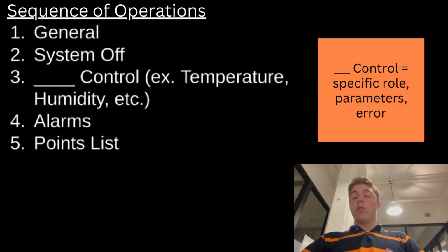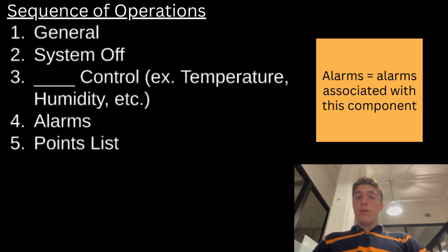3, blank control. So this could be humidity control, temperature control. Basically, it's describing what the equipment will be doing a little more in detail. So for example, it will explain how it will run once the system starts. So whether it's going to be running continuously or on intervals, the specific temperature or pressure or set point it will be sent to, and the allowable error. Next, there's alarms. This is a synopsis of the alarms that it's going to be connected to. For example, a heating coil is tied to a space temperature sensor, a supply air temperature sensor, and an airflow sensor. And if any of these pick up an anomaly, which is defined in the sequence of operations, then an alarm will go off. For example, if the temperature is more than 4 degrees above the set point for more than 10 minutes while the equipment is running, then an alarm will be sent to the BMS.